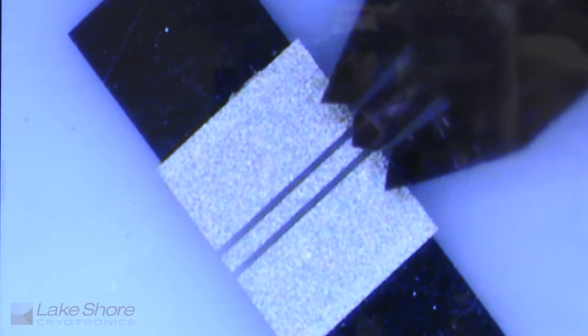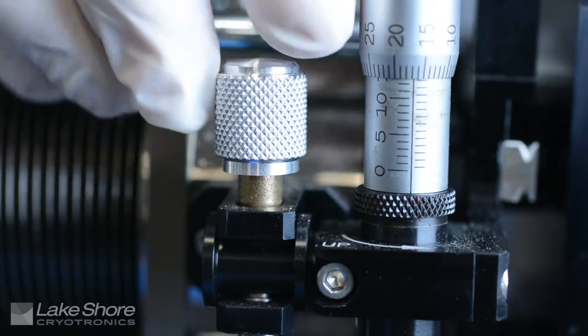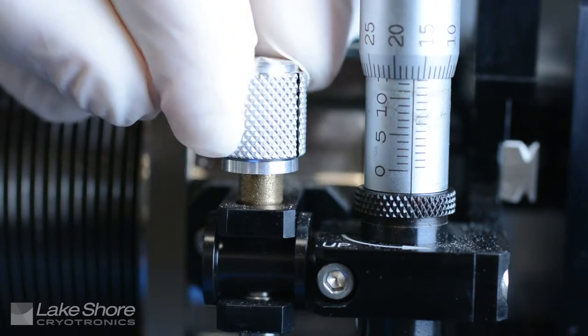While observing the probe tip through the microscope, use your probe station's probe x-y planarization adjustment and visually adjust until the probe tips appear parallel to the x-y plane.